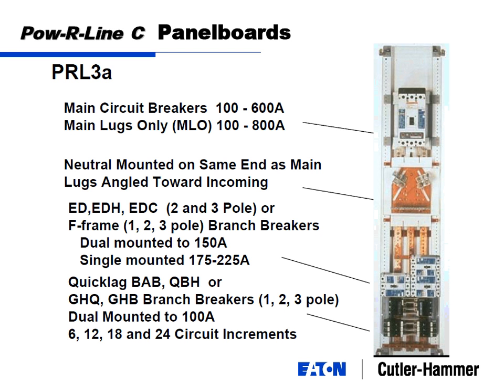So if I got an application where I need 20 of these things, but I don't want to put in big breakers, I want the cost-effective ones, so I can put in one panel board with, say, 20 of these cost-effective breakers, but I got 3 225 amp loads that I also want to feed. Maybe I've got 3 225 amp downstream panels I want to incorporate. So now I can mount this 225 amp breaker right next to it on the same chassis. So it's a combination power distribution panel, lighting and receptacle panel. Therefore, it's a more cost-effective way where I'm only installing one panel for both needs.